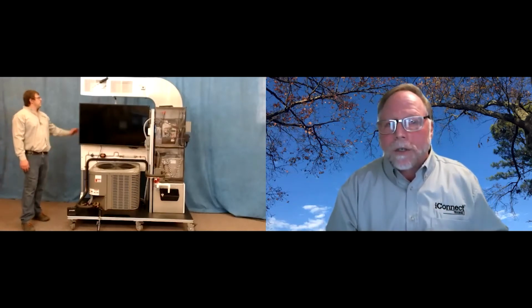Well, if we go over, and I've got the students there, and we've got the gauges going, on the screen and on our iPad, we can see the normal operating pressures. And I go over to that box over there, and I flip the condenser fan motor off, kill it. Before I do that, I ask them what they think is going to happen if we lose the fan. As they ramble through what they think is going to happen, I have them explain why they think that. And so we get into discussing heat transfer, condensing, and saturation temperatures, and how that affects the cooling.